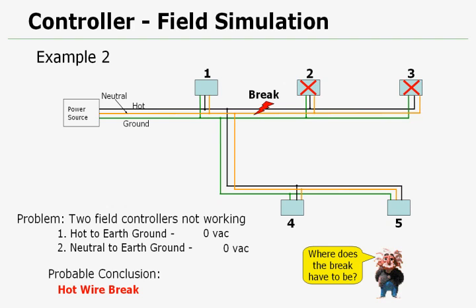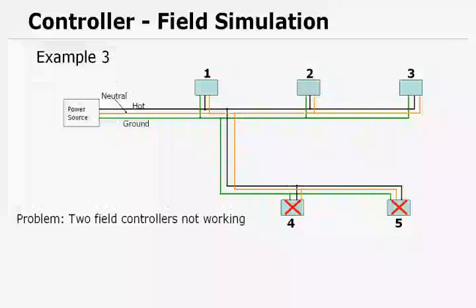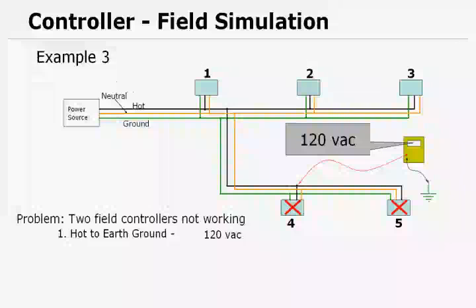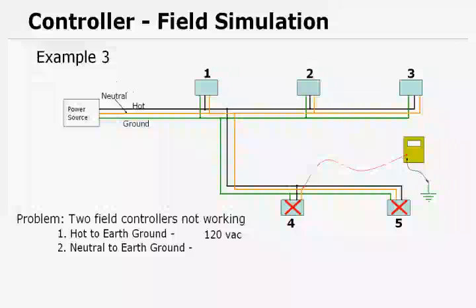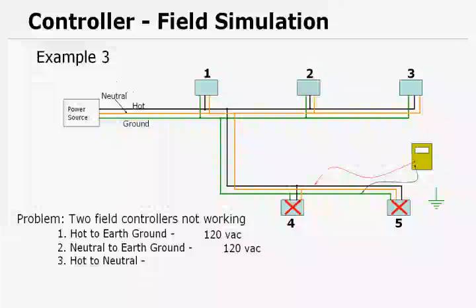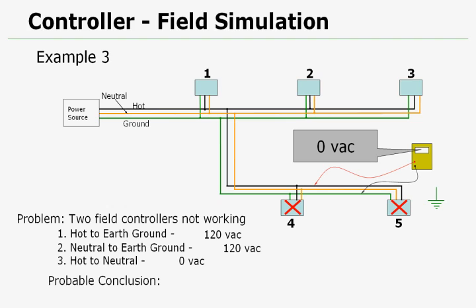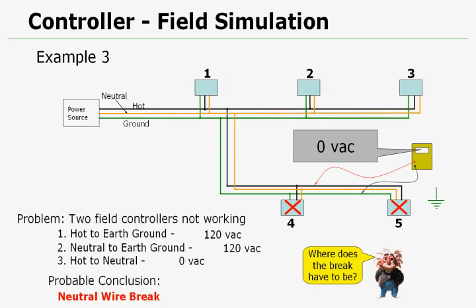Example three. Two field controllers are not working, but it's a different two in this example. It's controllers four and five. We do the same tests. Hot to earth ground, find that we have 120 volts AC at the first controller that's not working. Second reading, neutral to earth ground. And we find that there also we have 120 volts AC. So again, neutral to earth ground, we should have a reading of 0 to 5 volts, nothing more. So from what we've already learned, we already know we have a break in the neutral wire. Hot to neutral reading though, we get a zero reading. So probable conclusion is we have a neutral wire break. Now where does the break have to be? Well, we know it has to be between the last controllers that are working and the first controller that isn't working.